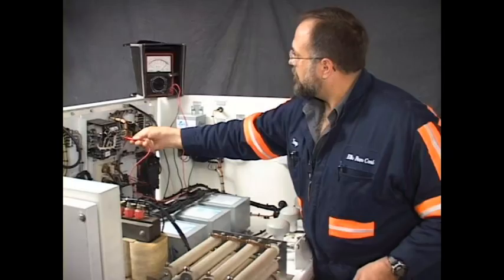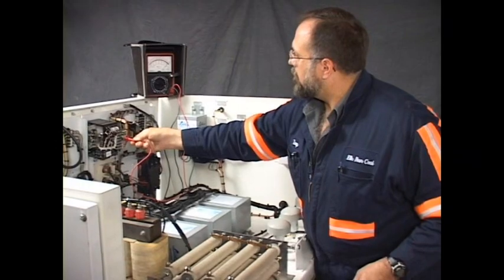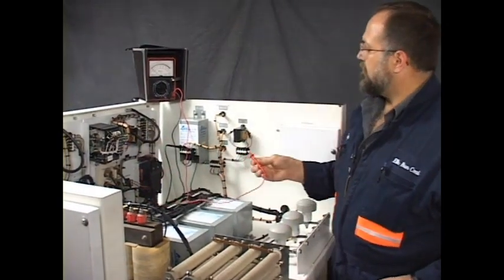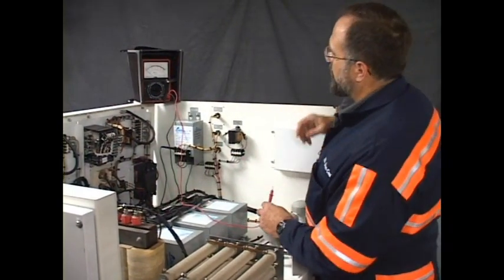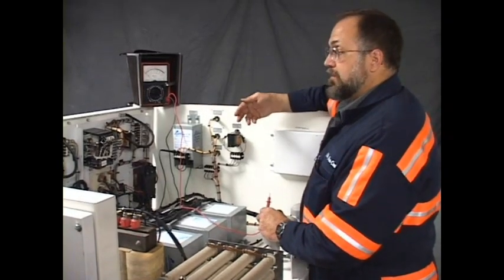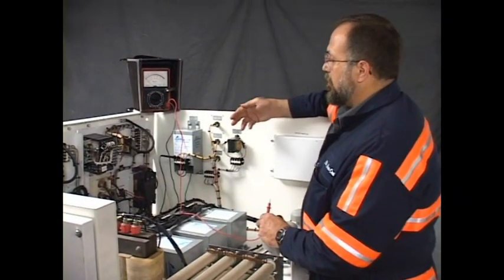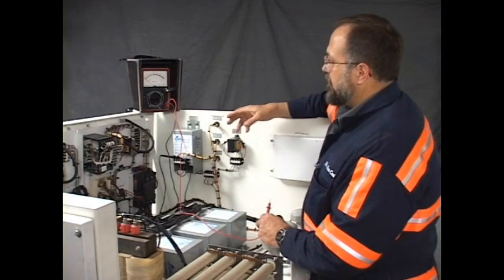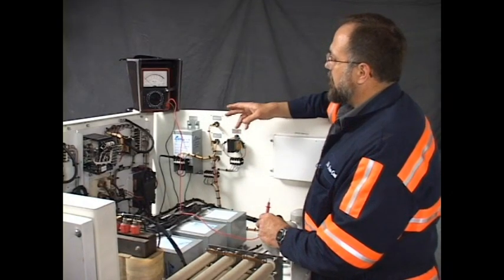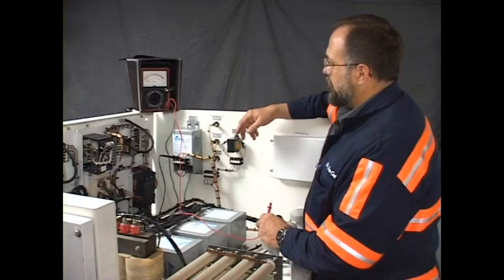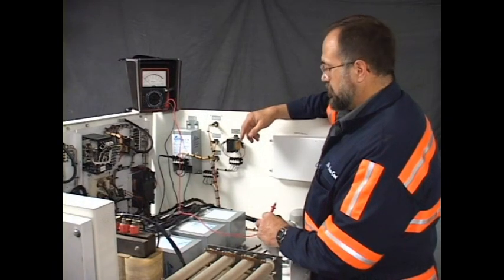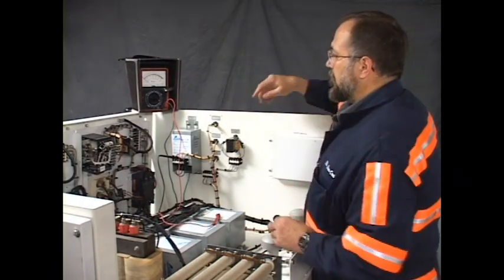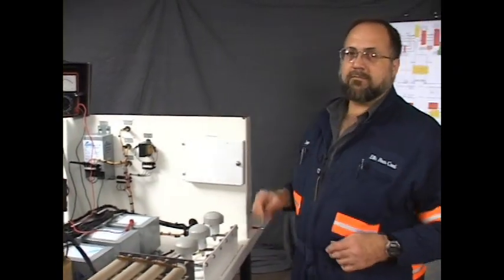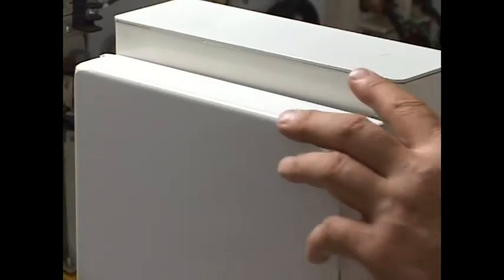You can put your meter to it. You'll see a small amount of cable resistance. All conductors have some resistance. That's a small amount. And where you attach your probes can also cause just a tiny amount. And that doesn't indicate an open. Okay, that is how the circuit should read. That is a proper circuit for the secondary of the control circuit. Now we're going to install the problem.